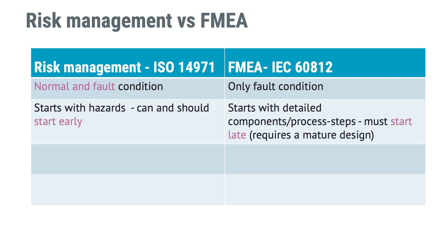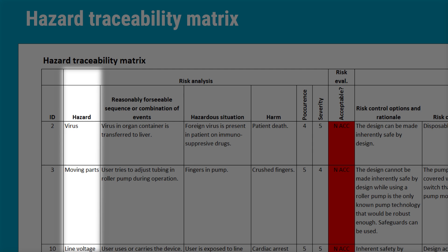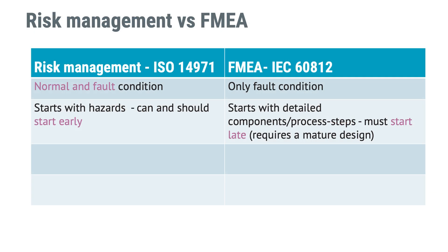If you remember the hazard traceability matrix I showed you as an example of what risk management is about, you've seen that we started with hazards on the left-hand side in the table. Hazards are potential sources of harm. The good thing about starting your risk management work with hazards is that in most cases you can identify the most important risks without doing any detailed design whatsoever. In fact, you're likely to be able to come up with quite a few important risks already in the conceptual stage of product development. Typical hazards could be viruses or bacteria, electricity, sharp edges, or toxic residues from production. Finding risks at an early stage usually saves a lot of money compared to finding them and having to mitigate them later on — or even worse, after you've released your product to market.